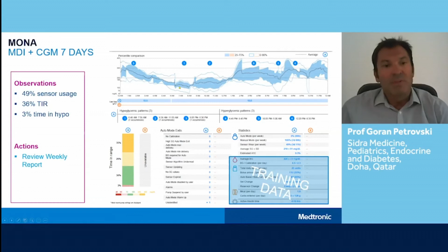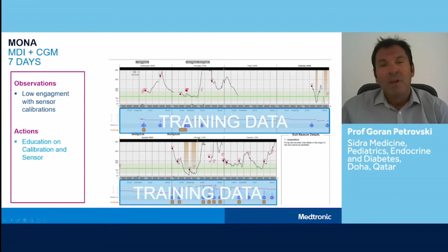As you know, this is the virtual onboarding protocol. We educated the patient on how to do regular calibration. We advised the patient to do 2 to 3, mostly 3, calibrations per day, and to have continuous sensor use. We educated the patient on the calibration and also the sensor. Then we started the manual mode, again virtually, and I can say that from the educator point of view this was a little bit tricky, because filling the reservoir and filling the cannula was tricky, and we want to be sure that the patient fills without bubbles.